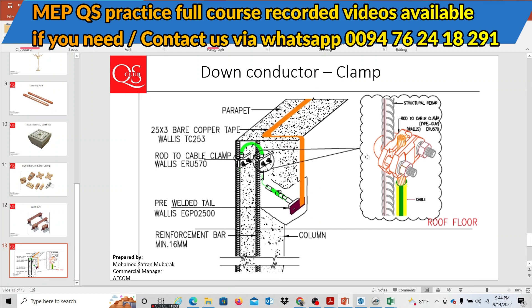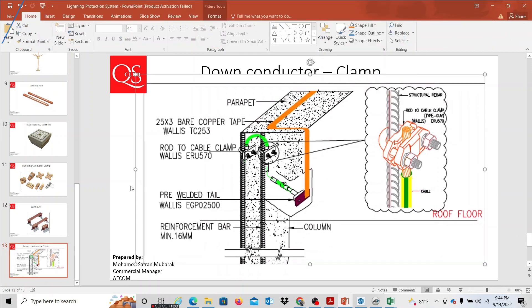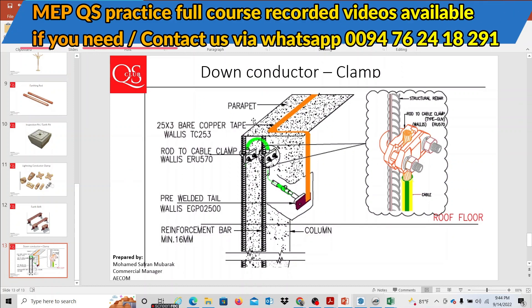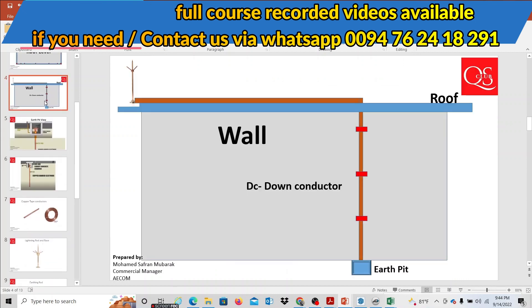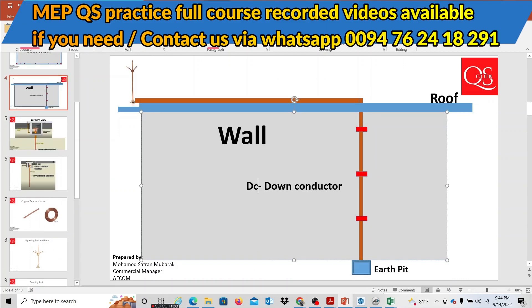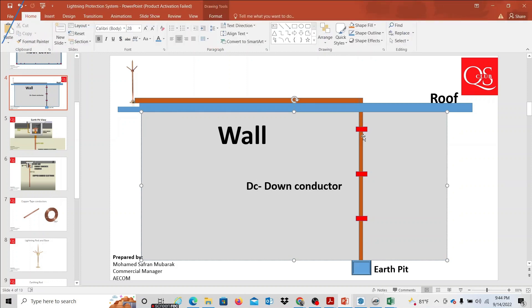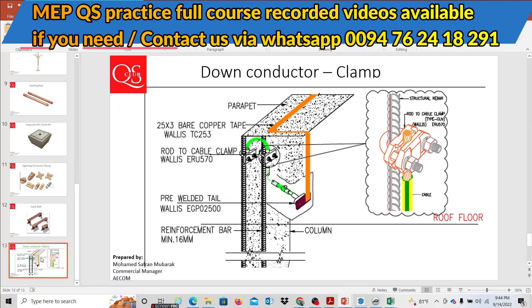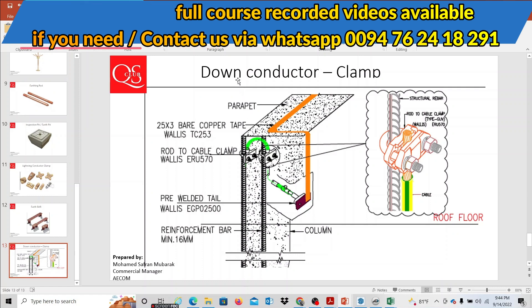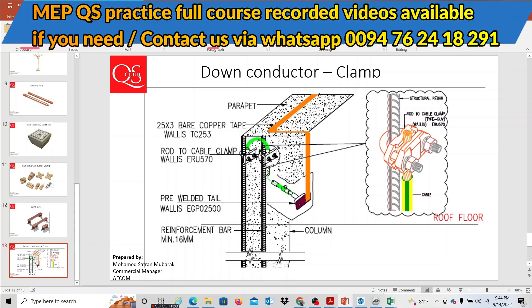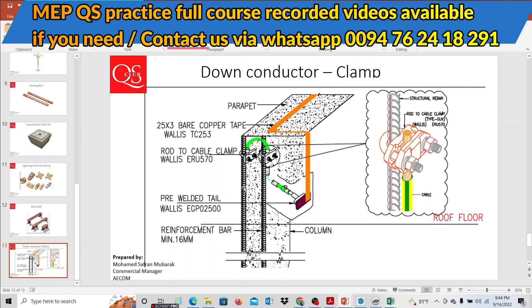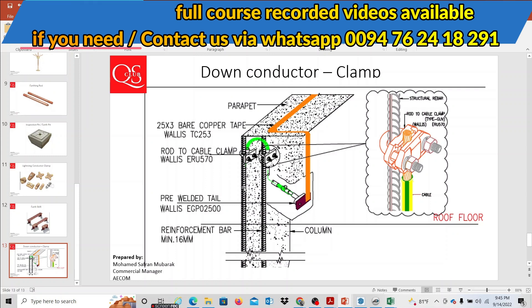This is a special setup for a high-rise building. The terminology used in this class is the down conductor and the down line. This is the general situation and the real situation in a high-rise building. The down conductor has a minimum 16 mm diameter with reinforcement.